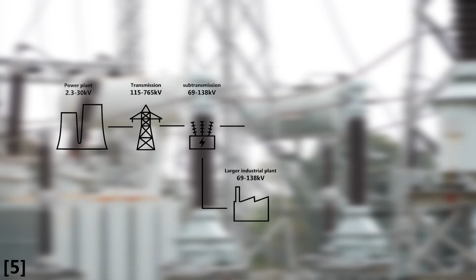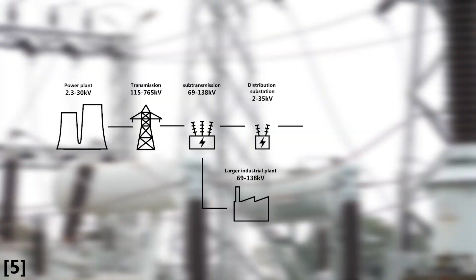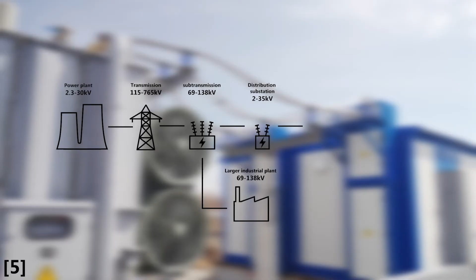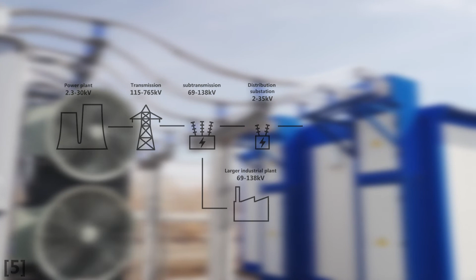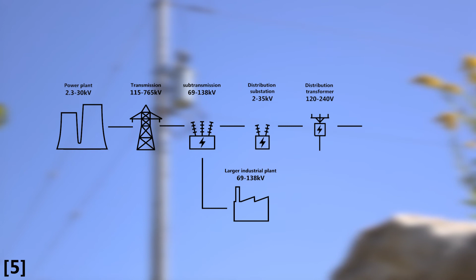But the voltage is still too high for most uses, so it is once again stepped down, this time at a distribution substation. Here, it is stepped down to a primary distribution voltage ranging from 2 to 35 kilovolts and typically serves a town or areas of a city. Finally, a distribution transformer, which usually covers individual neighborhoods, steps down the voltage one last time to either 120 or 240 volts depending on where you live, before the electricity is able to be used to power your home.